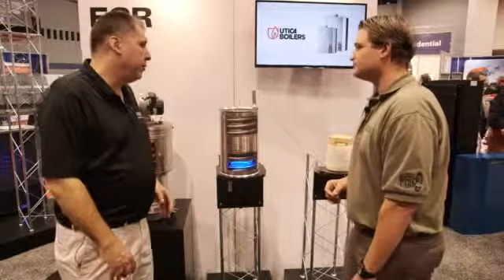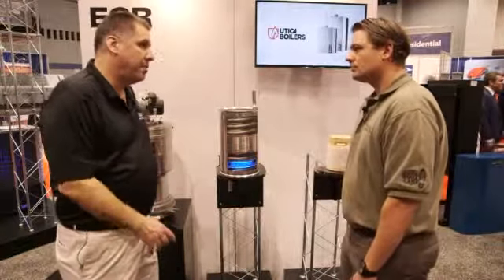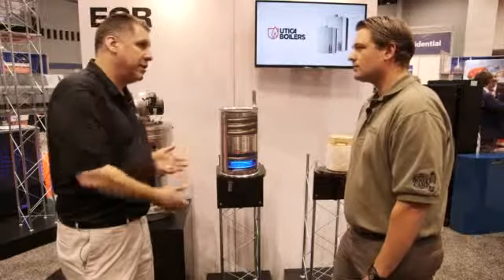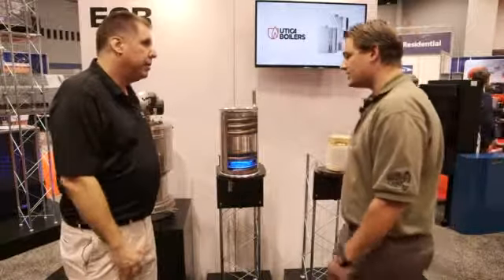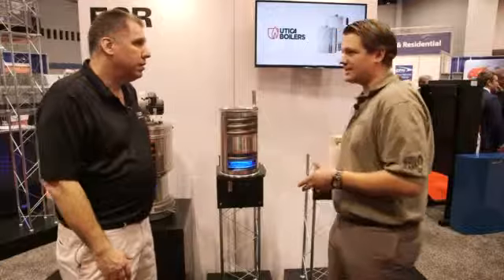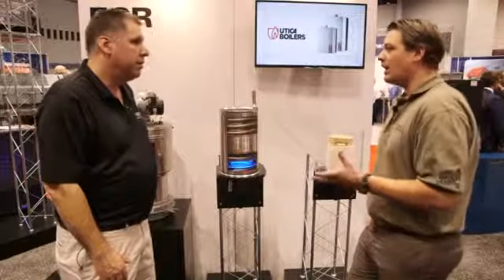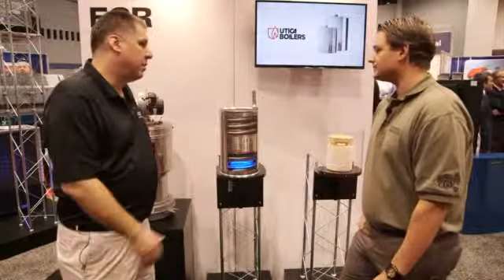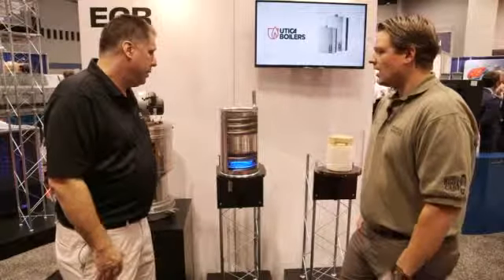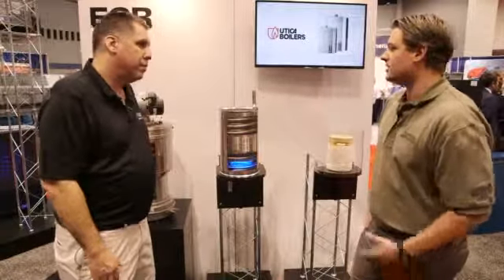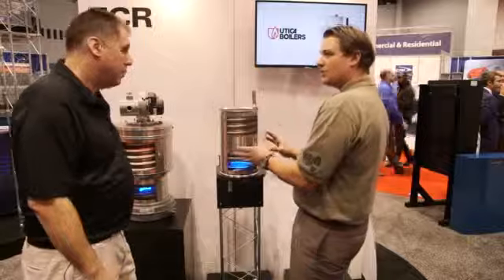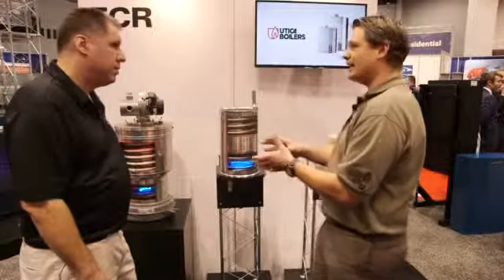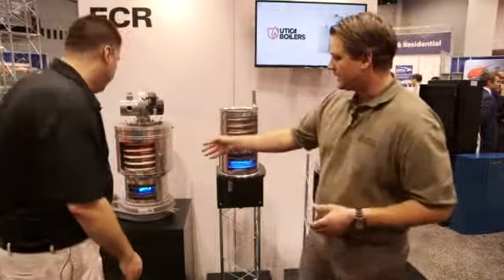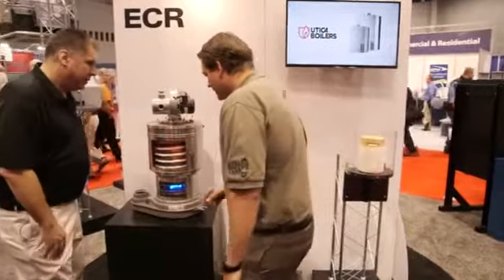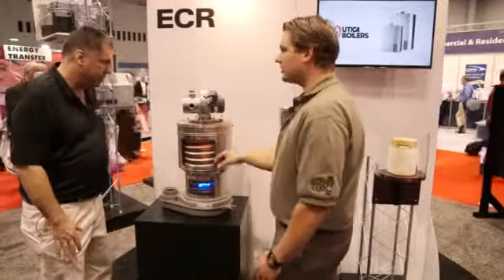Simon, in my market, we require an ASME H stamp on all our boilers. Does your heat exchanger carry that H stamp? We do carry an H stamp. We're actually rated at 150 PSI, which is very high for this market. Sure, so you can use it for commercial applications as well. Speaking of commercial applications, from this base design, which is what we originally came out with, we developed a 299 boiler. Let's take a look at that. That would be this heat exchanger over here. So you have much more fin, much more tubing inside of it.